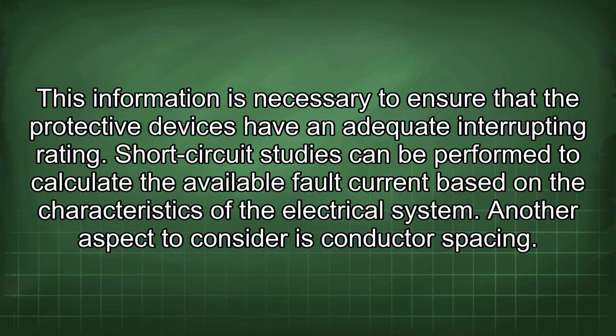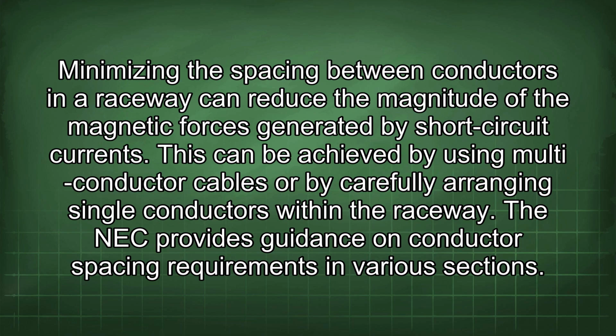Another aspect to consider is conductor spacing. Minimizing the spacing between conductors in a raceway can reduce the magnitude of the magnetic forces generated by short-circuit currents. This can be achieved by using multi-conductor cables or by carefully arranging single conductors within the raceway. The NEC provides guidance on conductor spacing requirements in various sections.